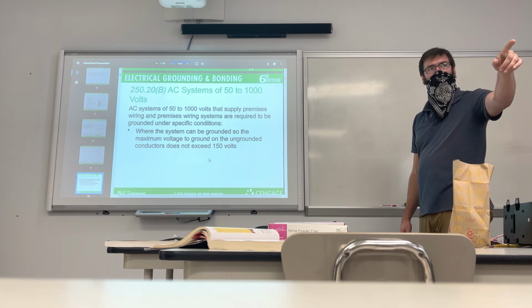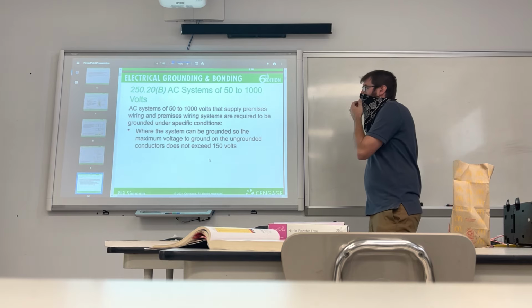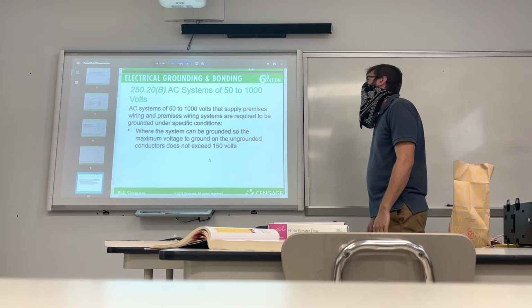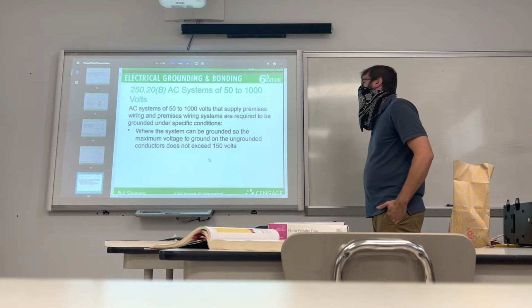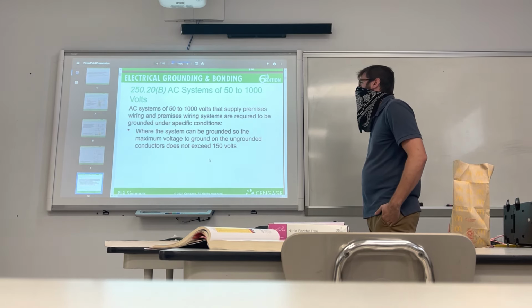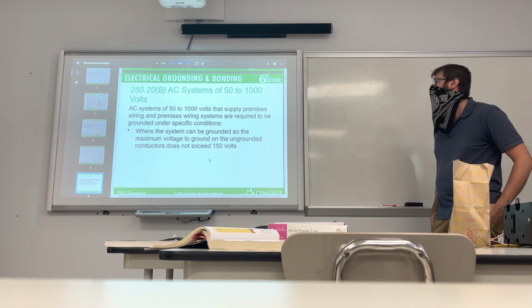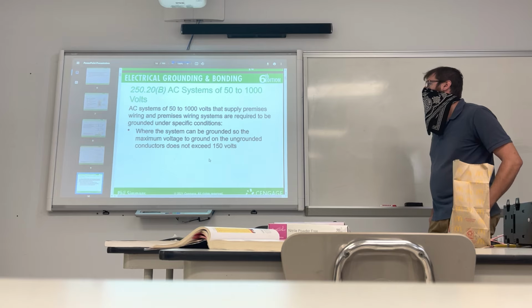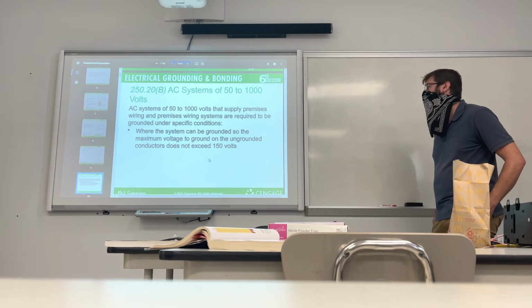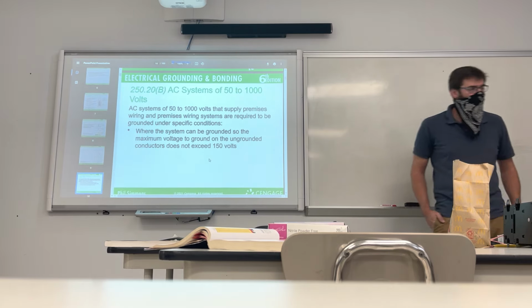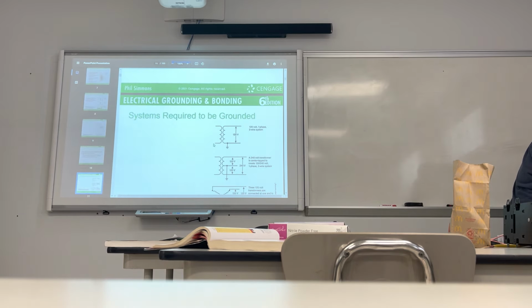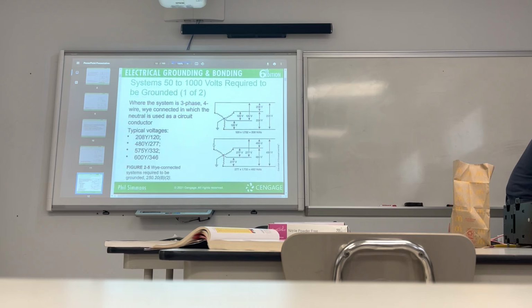Did you just read? Yeah. 250.20(B), AC systems of 50 to 1000 volts. AC systems of 50 to 1000 volts that supply premises wiring and premises wiring systems are required to be grounded under specific conditions where the system can be grounded so the maximum voltage to ground on the ungrounded conductors does not exceed 150 volts. Yeah, these are all just systems that have to be grounded.